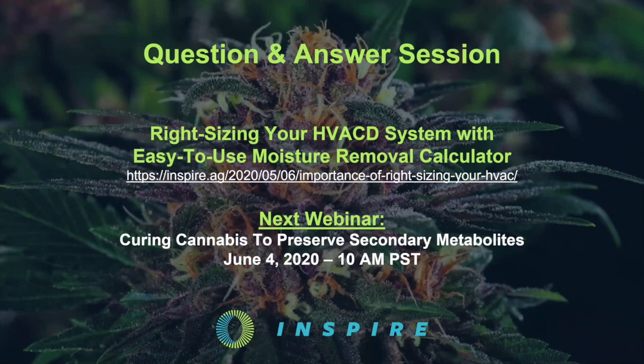Yeah, absolutely. I can tell you for sure that an unsealed, we'll start with the second question first. A concrete floor, we've seen it in rooms contributing humidity into the space, almost 50% of what the plants were doing at different times of the stages of growth. Especially this is a problem in drying rooms. So if you're going to use a concrete floor, your best chance to combat that and not have to over dehumidify moisture inside your space that's not coming from your plant is to seal it off.